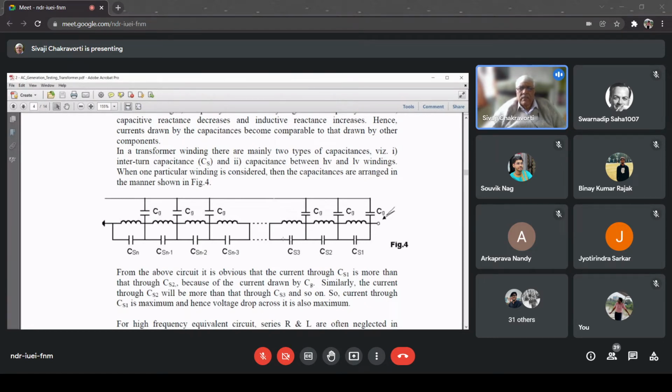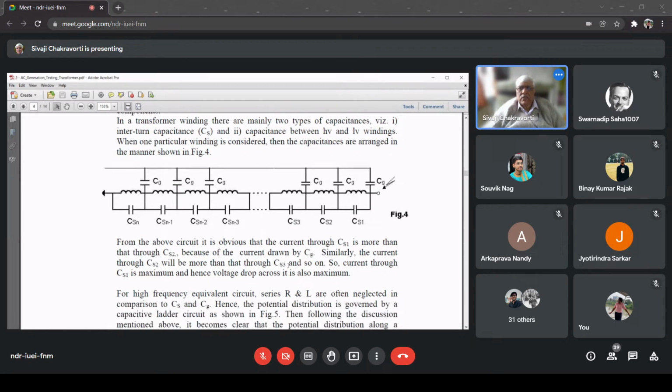But now here, what we are discussing at high voltage class is not just power frequency. We are talking about several types of high voltages where a lot of transients are there. So frequency, the equivalent frequency is much higher. For a lightning impulse, the equivalent frequency goes to of the order of megahertz. Now, when it is 1 megahertz, something interesting happens, that 1 by omega C, when this omega 2 pi f is 1 megahertz, this capacitive reactance becomes much smaller.